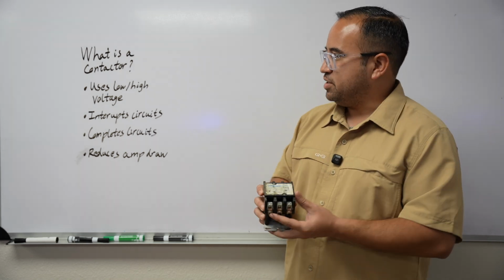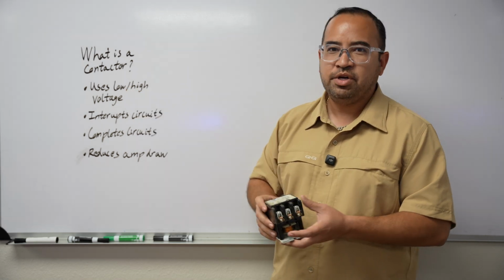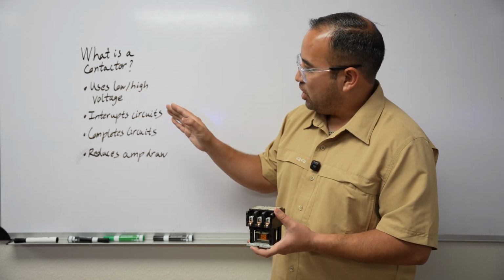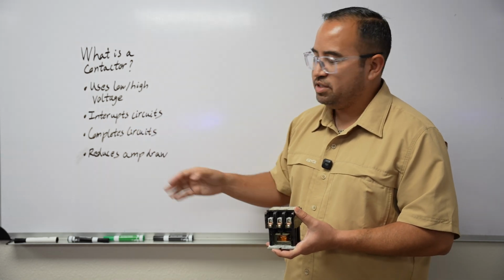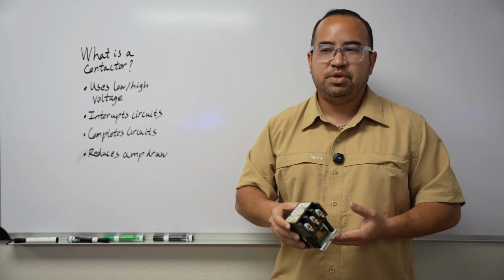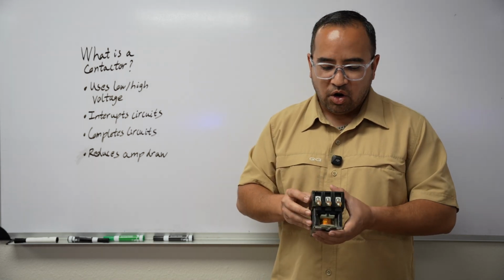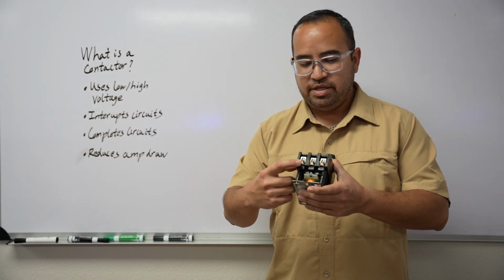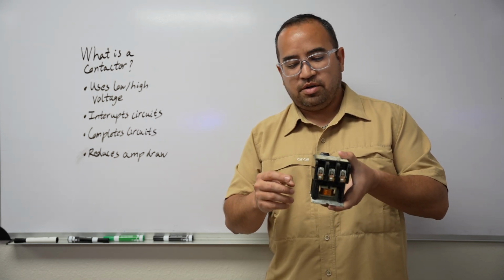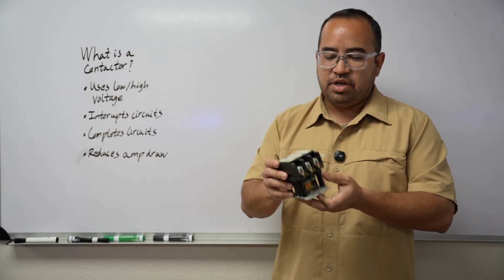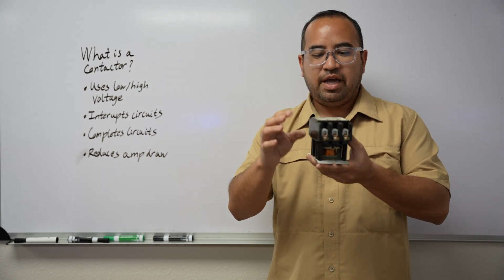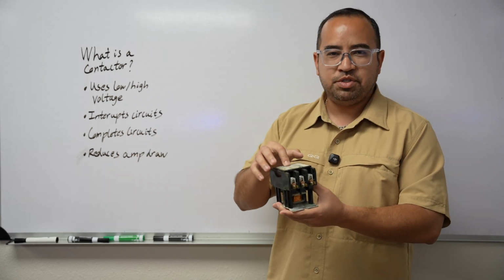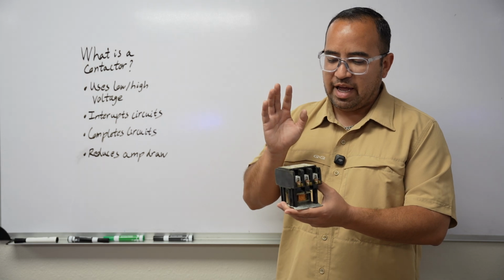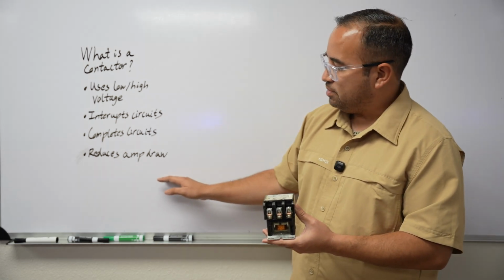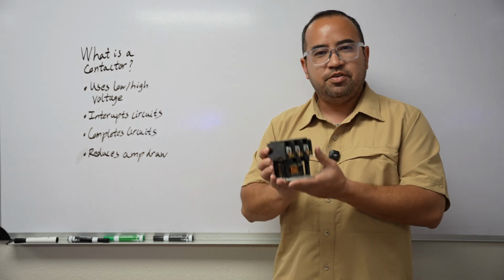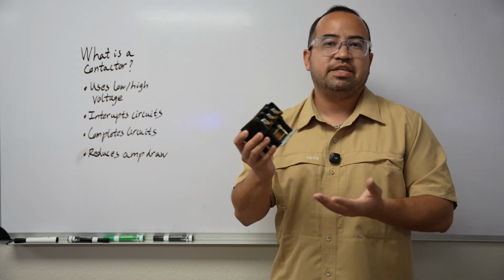The job of the contactor is to use low voltage and high voltage to make sure that we're either interrupting circuits or completing circuits. It does that by having something like the motherboard or the thermostat call the low voltage, which is right here on the side of this contactor, and on residential it may have it on the side too. When it calls, it pushes in the plunger and completes the high voltage circuit. What it does is reduce amp draws because it turns on different components depending on what the thermostat is asking for.